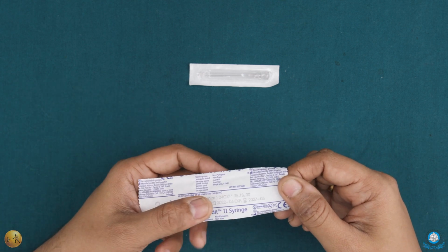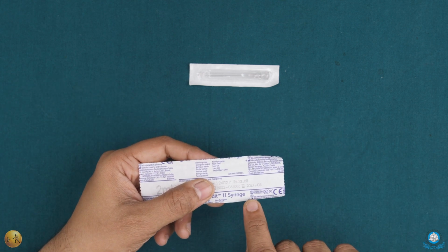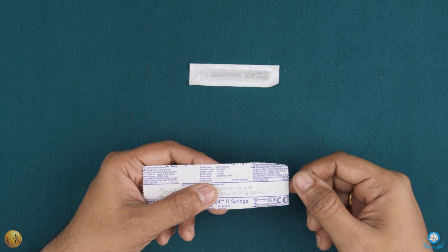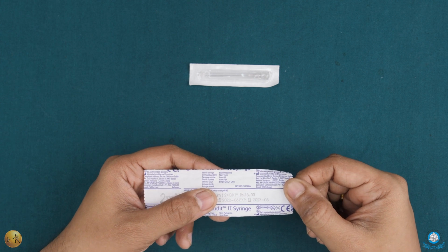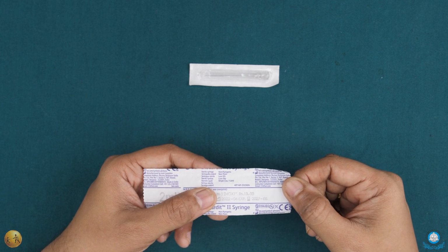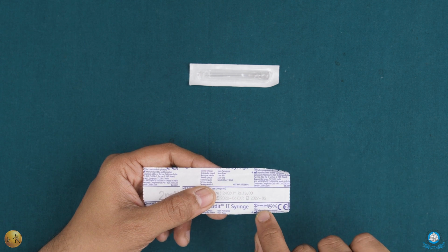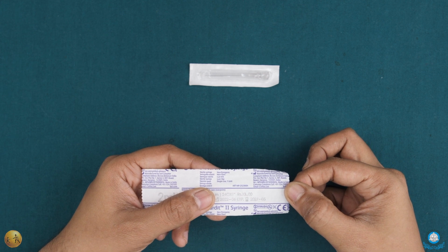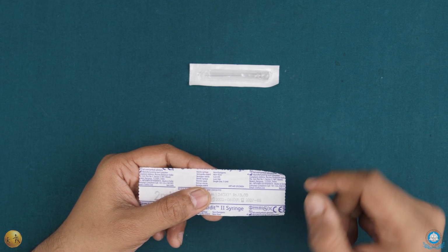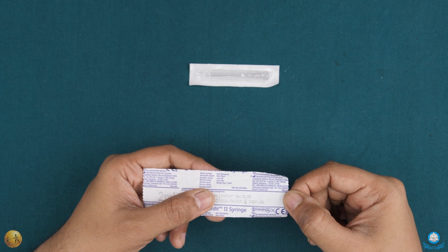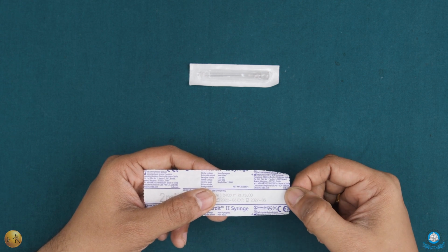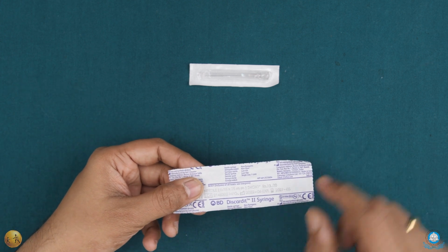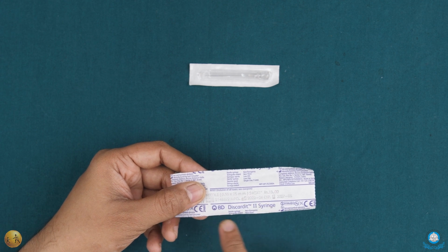Now if you notice these symbols here, you have the symbol where the 2 is crossed out. Now this 2 basically tells you that the instrument within this packaging should not be used more than once. You notice that it says sterile EO, that means this instrument has been sterilized by ethylene oxide. You then have a marking which specifically tells you that you do not autoclave this instrument.